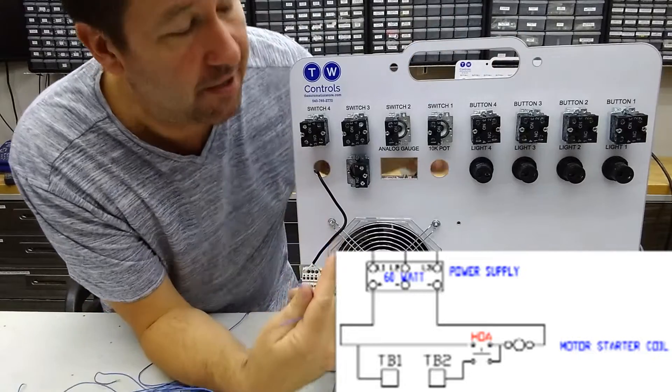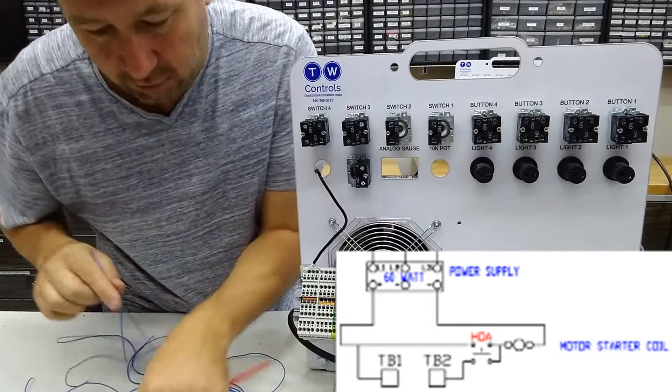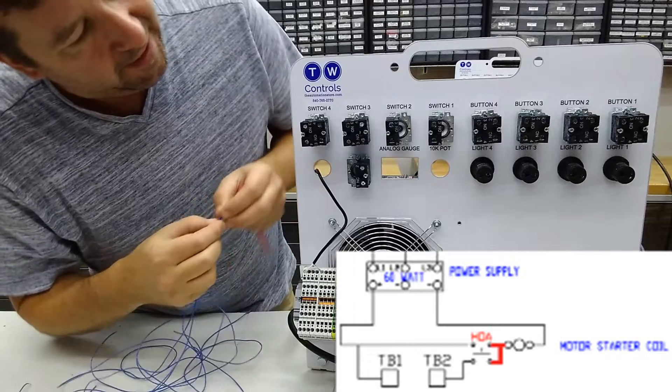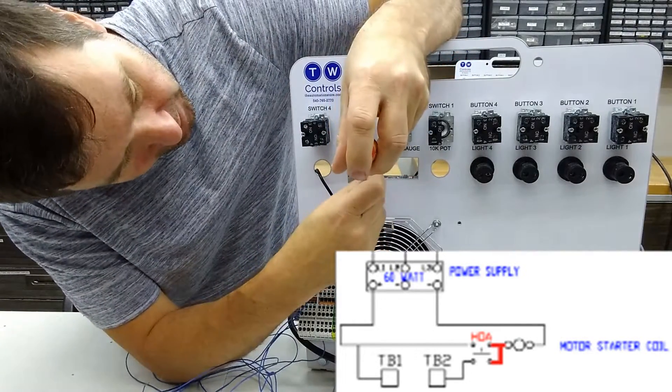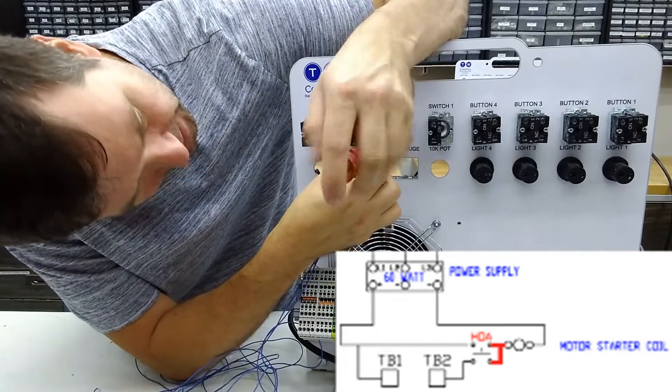So we're going to use this wiring diagram, which again is one of our standard control panel wiring diagrams. And we're going to start by connecting a jumper across the bottom contacts of this switch. They're both normally open contacts.